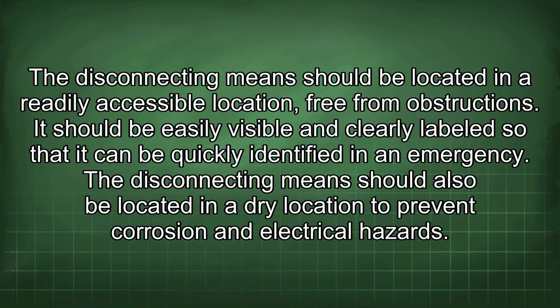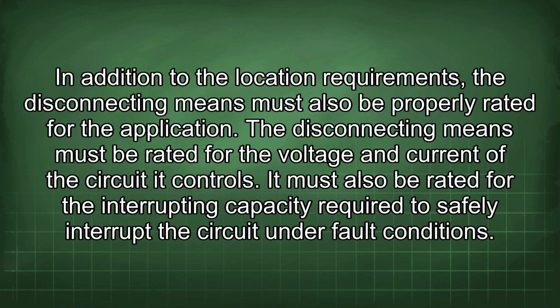The disconnecting means should be located in a readily accessible location free from obstructions. It should be easily visible and clearly labeled so that it can be quickly identified in an emergency. The disconnecting means should also be located in a dry location to prevent corrosion and electrical hazards. In addition to the location requirements, the disconnecting means must also be properly rated for the application.